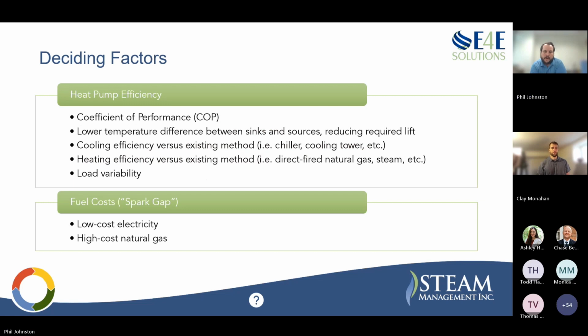As far as when to get a heat pump involved in these kinds of projects, it really comes down to your sources and sinks. Do you have a viable source of heat, and do you have a viable sink to put that heat in? Temperatures are also a big part of that. If you can't match up from a temperature standpoint, the heat pump's not going to work. The further those temperatures are apart, the bigger lift the heat pump has to work on, which is going to drive efficiency down, just like Clay overviewed before. So all those factors have to be evaluated and understood before you know if a heat pump's going to be viable or not. The other big angle of this is cost.